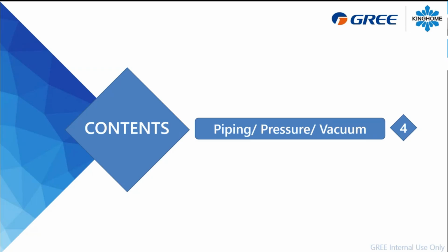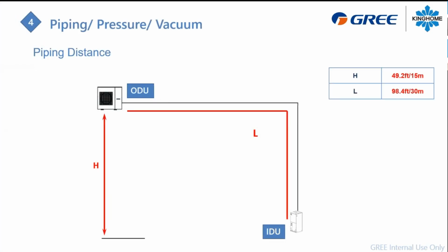So you already know how to do the piping stuff, but we're going to review it again, just to make sure. I've said it already, but from the outdoor unit to the indoor unit, you can't go further than 98 feet. And if it's, for example, installed on the roof, the height difference between those two units, the outdoor and the indoor unit, cannot be more than 49 feet.